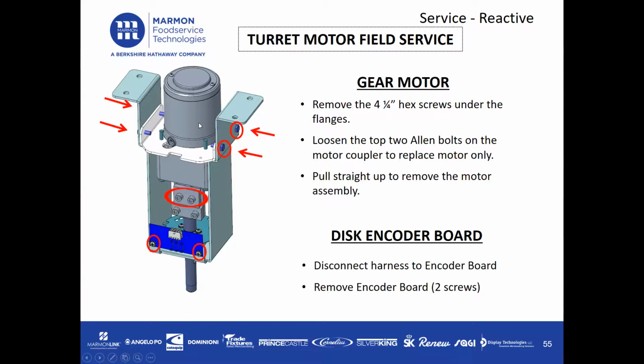Once you attach the new motor, you're going to want to use the same mounting bracket, slide it into the new motor, position it back in place, and resecure it by securing the 4 quarter-inch hex screws on the left and on the right, and securing your coupling to your turret motor shaft.